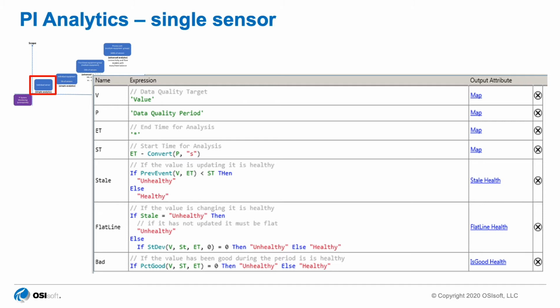Thinking more on the level that you're showing here with the individual tag quality. Yeah, so the problem is a little bit more involved. You can use a watchdog tag to do it, but we also have other capabilities because sometimes, let's say you are trying to do some averaging or some totalization on some number, what you want to make sure is that 50% of your data is not bad. You are willing to maybe tolerate 5% bad quality data. So on top of the calculations for healthy and unhealthy that I've talked about here, there are also additional functions available. We call that a percent good function, and you can apply that to the averaging or some of the aggregations that you're trying to do.